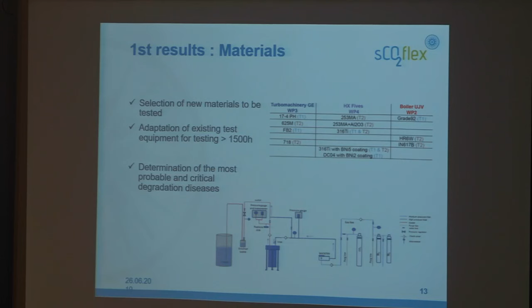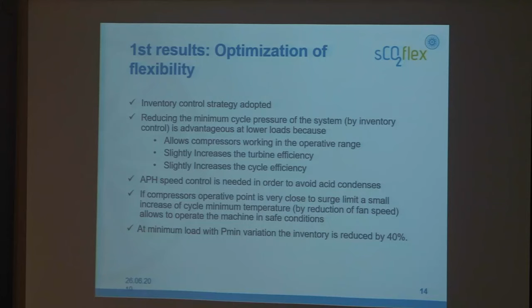We optimize the flexibility, so we will adapt to an inventory control strategy. It's quite new, but it's simpler to manage the cycle for supercritical CO2. We reduce the minimum cycle pressure of the system with the inventory control. We still need speed control in order to avoid acid condenses in the cycle, and now we are dealing with the operation of the compressor just near the critical point, and how to work with this inventory system. Maybe we can have only one storage, or maybe several smaller storages at different parts of the cycle.